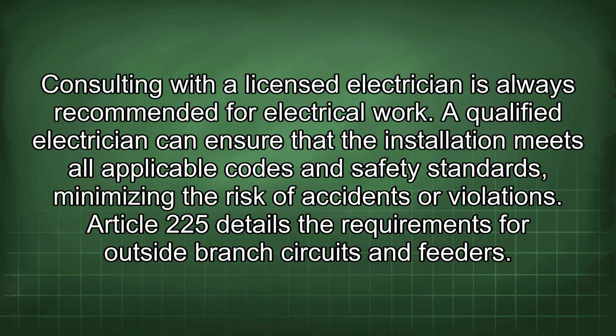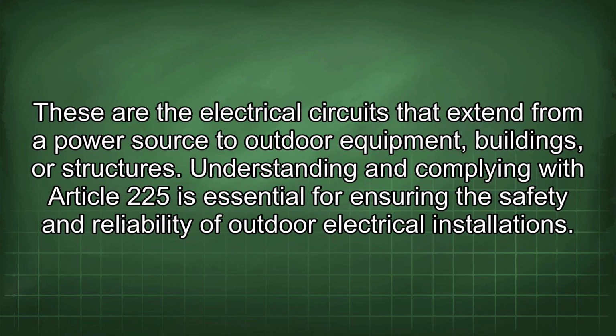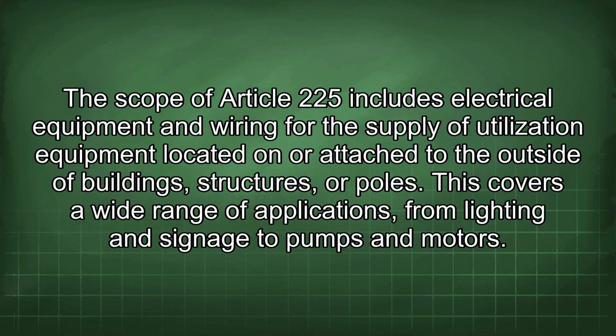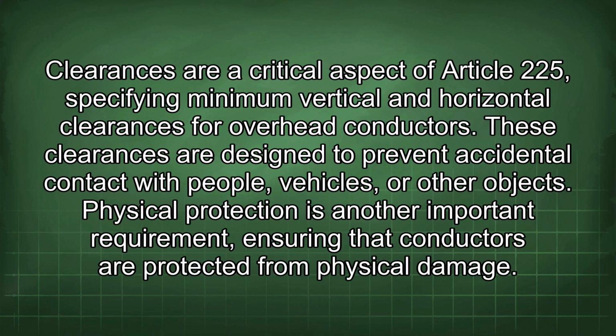Article 225 details the requirements for outside branch circuits and feeders. These are the electrical circuits that extend from a power source to outdoor equipment, buildings, or structures. Understanding and complying with Article 225 is essential for ensuring the safety and reliability of outdoor electrical installations. The scope of Article 225 includes electrical equipment and wiring for the supply of utilization equipment located on or attached to the outside of buildings, structures, or poles. This covers a wide range of applications from lighting and signage to pumps and motors. Clearances are a critical aspect of Article 225, specifying minimum vertical and horizontal clearances for overhead conductors. These clearances are designed to prevent accidental contact with people, vehicles, or other objects.